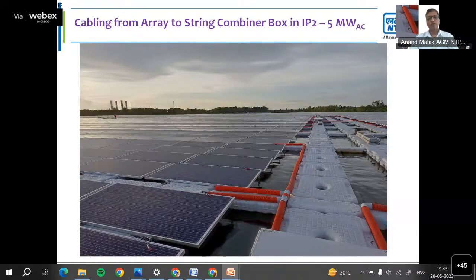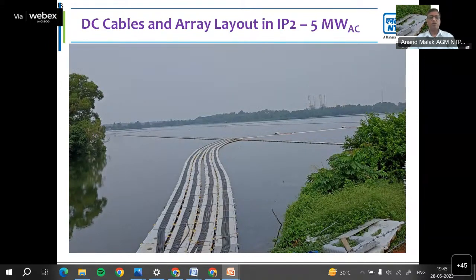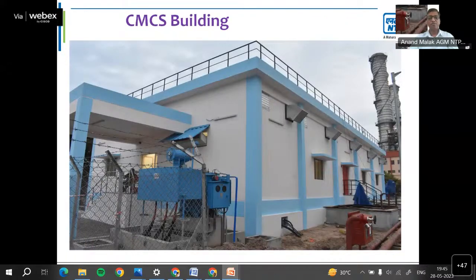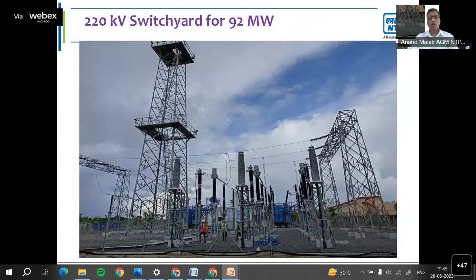This is another view. All the DC cables from the string combiner box, one positive and one negative, come from the field to the inverter. And this is the CMCS building which was constructed for the 92 megawatt floating solar plant. We have a small auxiliary transformer for the auxiliary power requirement of the HT panel. And these are the two power transformers. We have the firefighting system, that is the HVWS, high velocity water spray system. From here, the power goes through underground cables to our gas insulated substation.